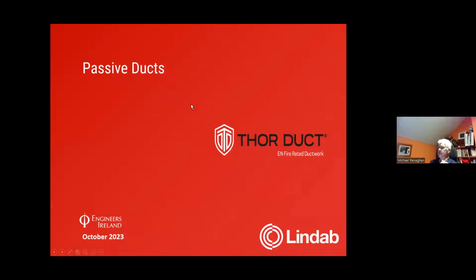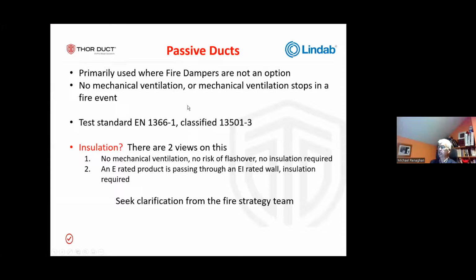Okay, so passive ducts. What is a passive duct? Well, passive ducts are primarily used where fire dampers are not an option, or ducts that have no mechanical ventilation. And so no mechanical ventilation, or mechanical ventilation stops in the event of a fire. So they can either have it or it shuts down in the event of a fire. The idea here is that people would think, well, what type of standard should it be? It should be to the EN standard, it should be classified 13501-3. But there's a big question.